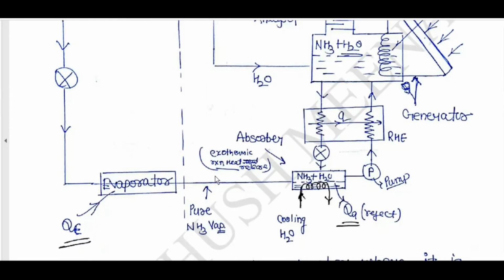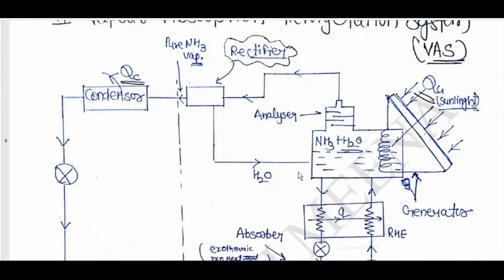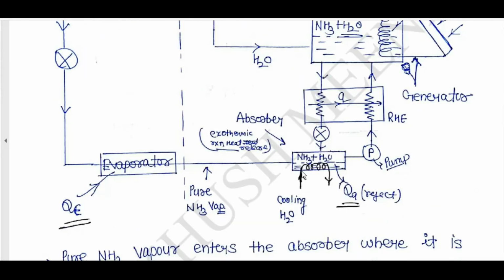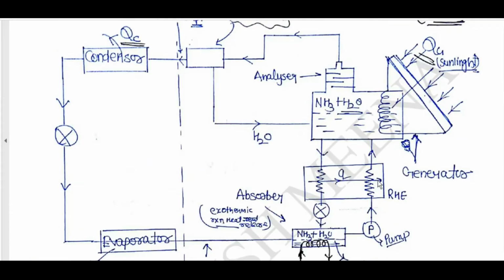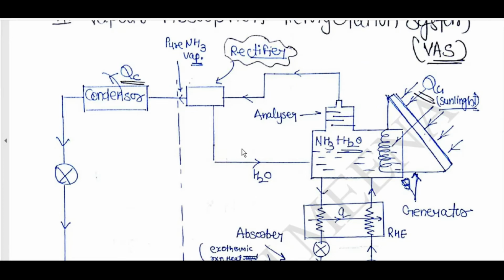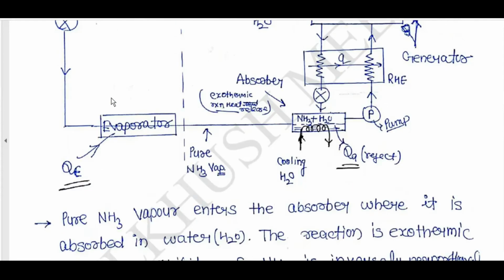NH3 vapor will first go through the NH3 H2O solution, where Q_A is rejected. The NH3 plus H2O is pumped and heated by Q, which is sunlight. From the sunlight it is used in the analyzer. Then H2O is separated and NH3 is sent on. Now through the rectifier, pure NH3 vapor passes through the condenser.